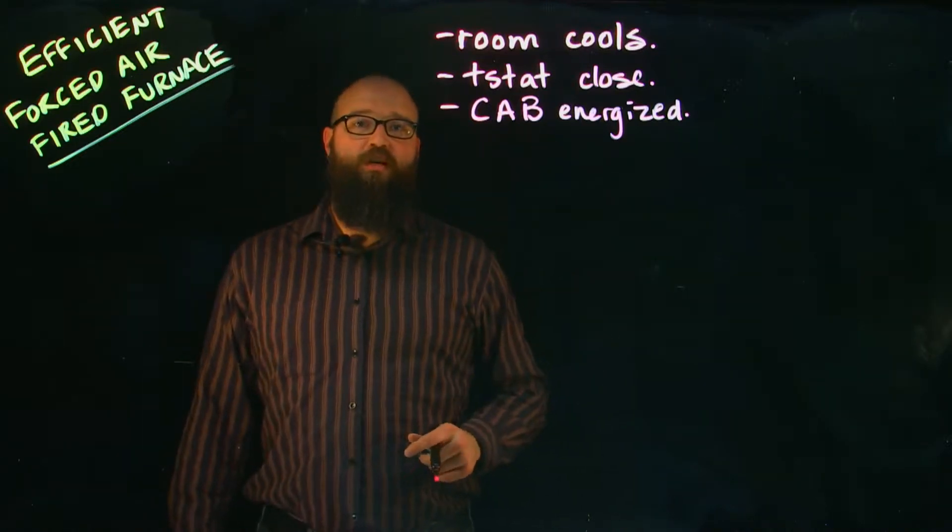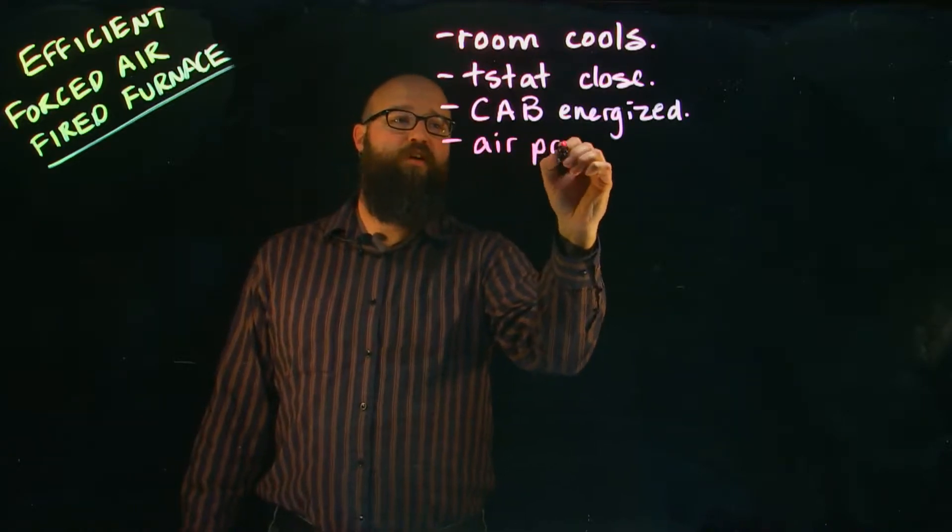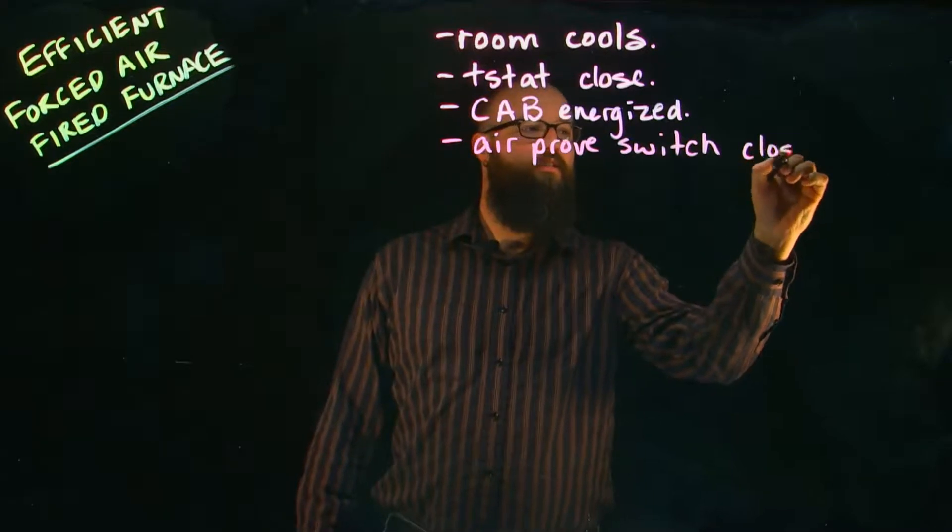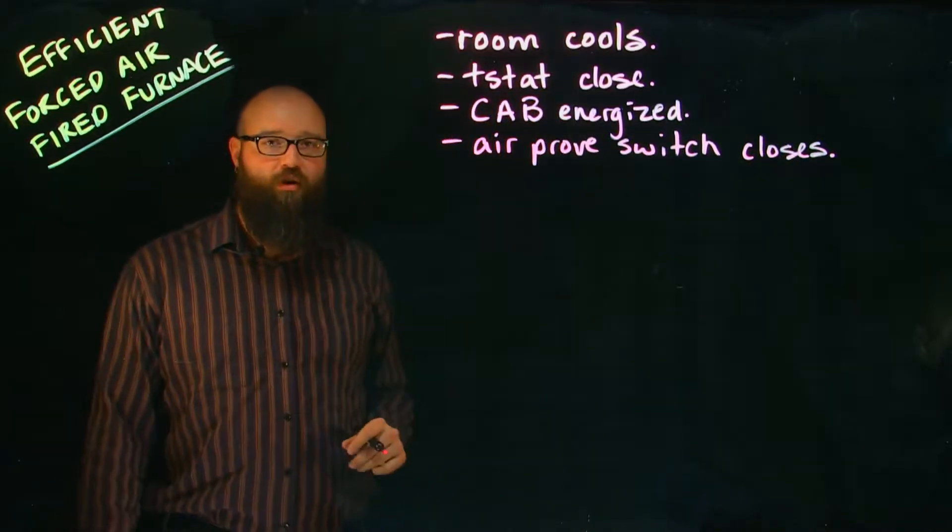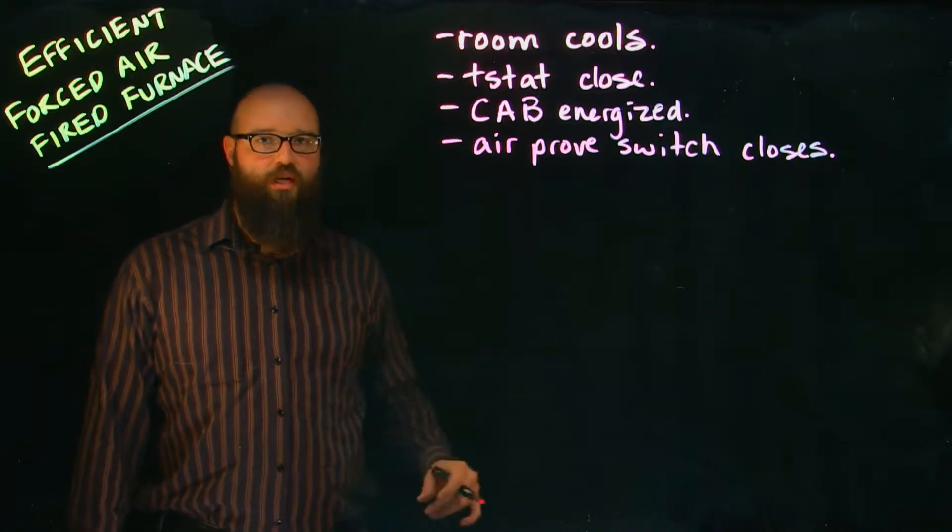Once our combustion air blower is energized, it creates a negative pressure and our air prove switch closes. That sends a signal back to our electronic control board, which then says it's safe to now start the ignition sequence.